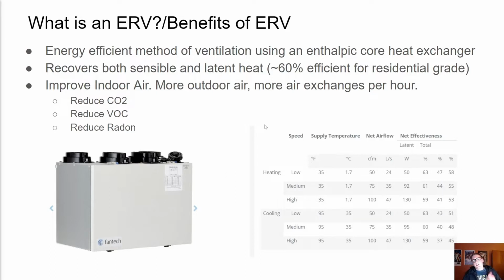So you've got an inlet coming in from the outside of your house, you've got an outlet, and then you've got that return air, and then you have that new fresh supply air. For a residential ERV, that efficiency is around 60%. And so that recovers both sensible and latent heat. So you're moving diagonally on the psychrometric chart. On the next slide, I've got how you can decide whether you want an HRV, which just does sensible heat, or an ERV, which does sensible and latent. So that essentially recovers some energy from both the temperature and humidity of the air.